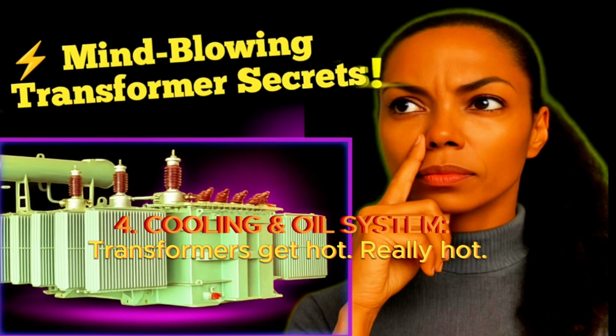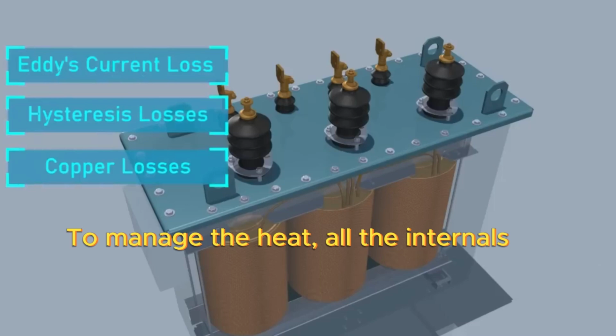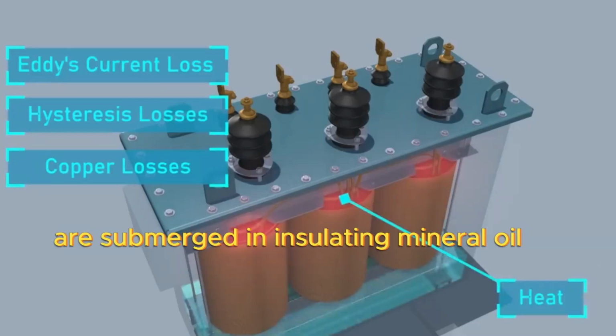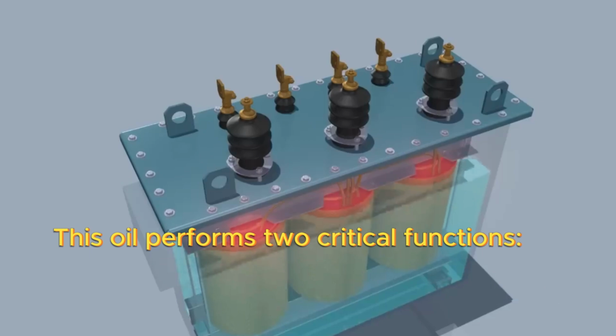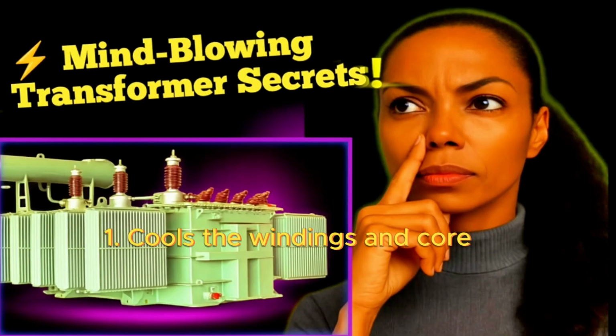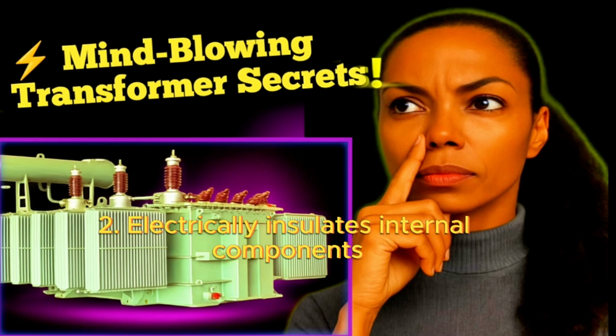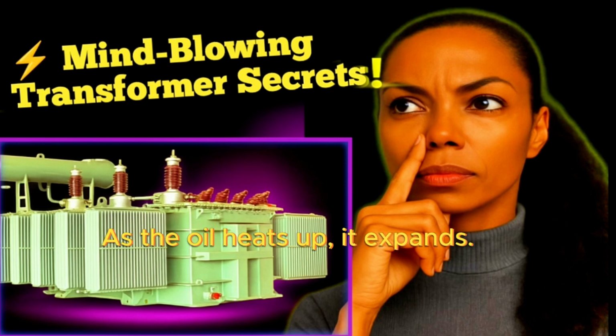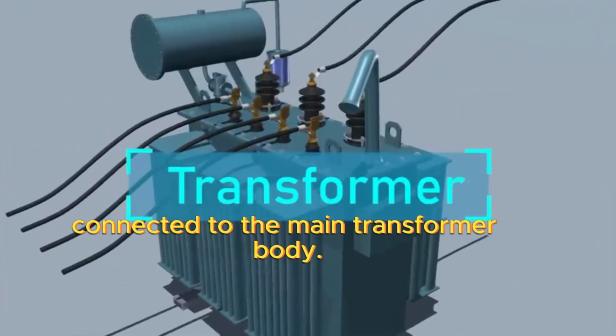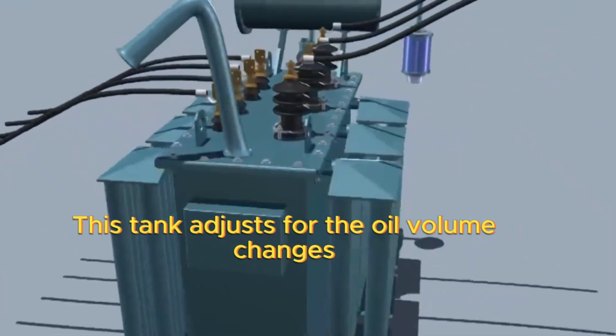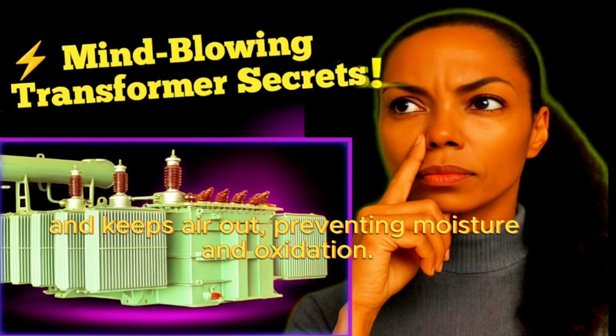Cooling and oil system. Transformers get hot, really hot. To manage the heat, all the internal parts are submerged in insulating mineral oil. This oil performs two critical functions. Number one, it cools the windings and core. Number two, it electrically insulates the internal components. As the oil heats up, it expands, so we use a conservator tank connected to the main transformer body. This tank adjusts for the oil volume changes and keeps air out, preventing moisture and oxidation.